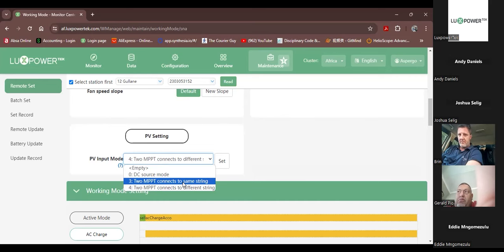you've got 10 panels on the roof, right? So you're going to put 5 in the one string and 5 in the other. But what you want to do is parallel the strings on the roof and only bring down one set. So by paralleling them, what happens is that the voltage stays the same, but the current increases, it doubles.